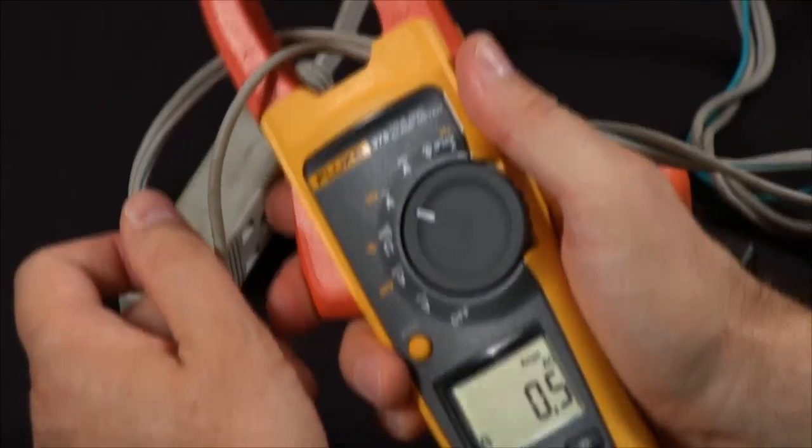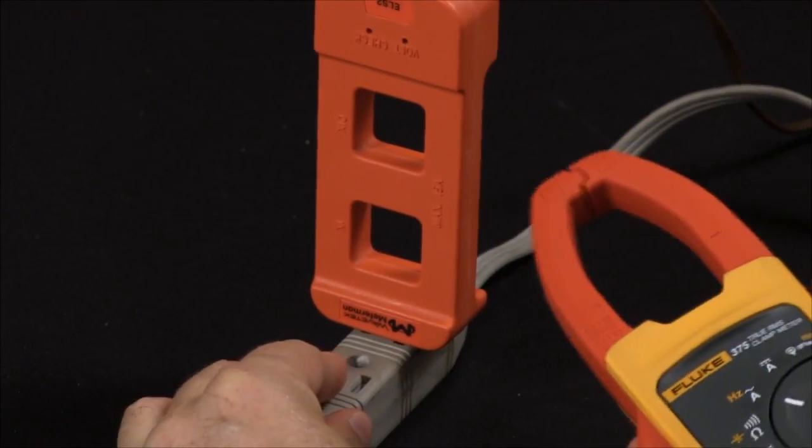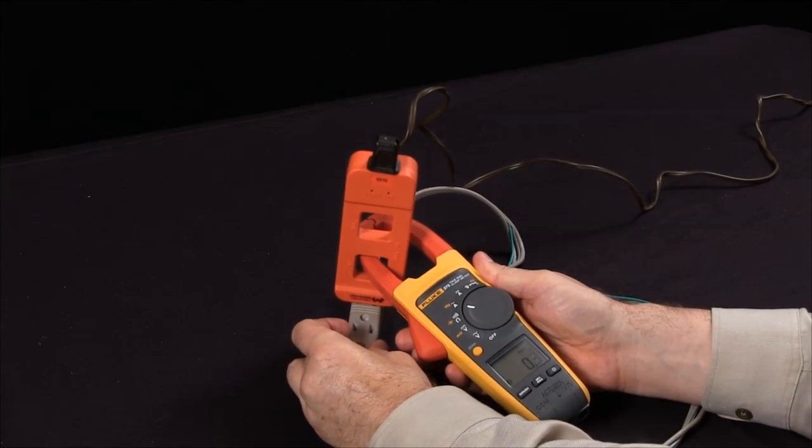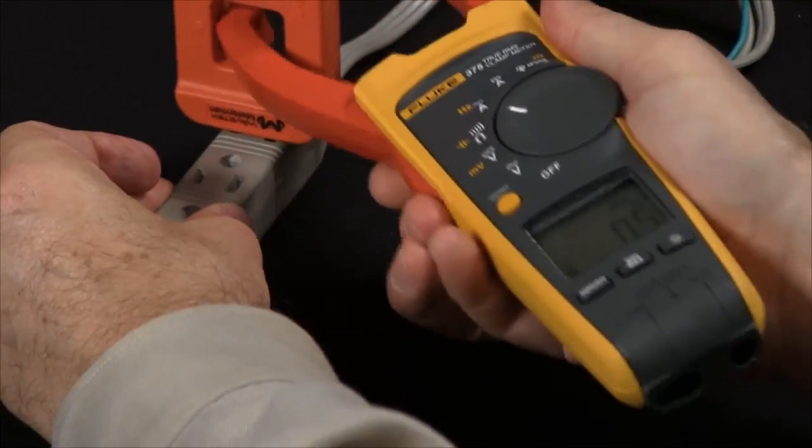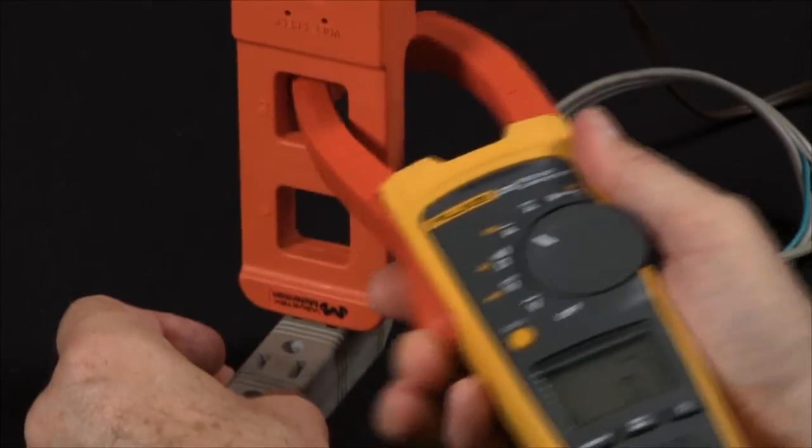Now, this is also a good application to use one of our line splitters. I have an x1 and an x10 winding, so measuring through the x1, you'll see I have the same indication on my screen, just about a half an amp.